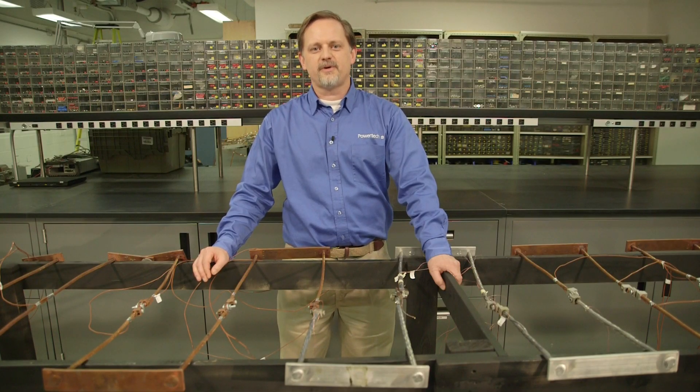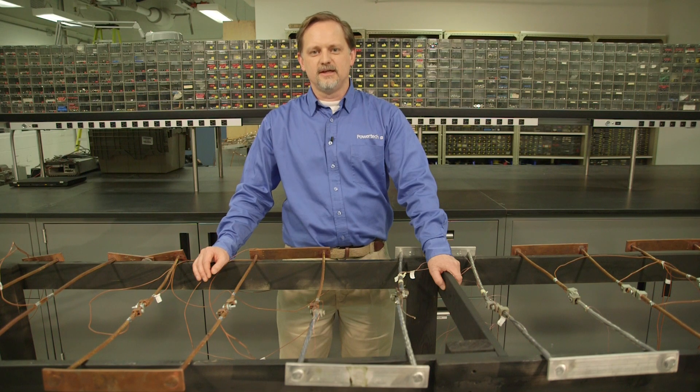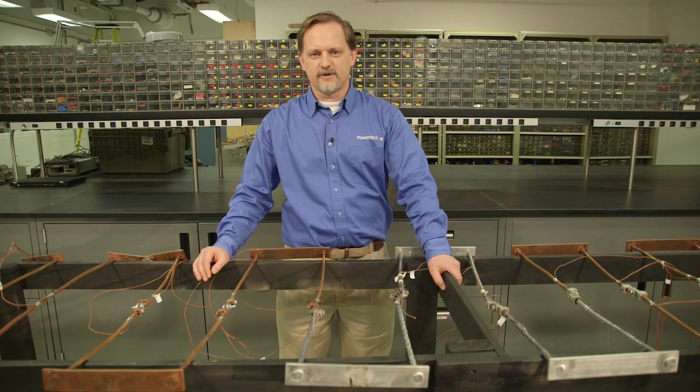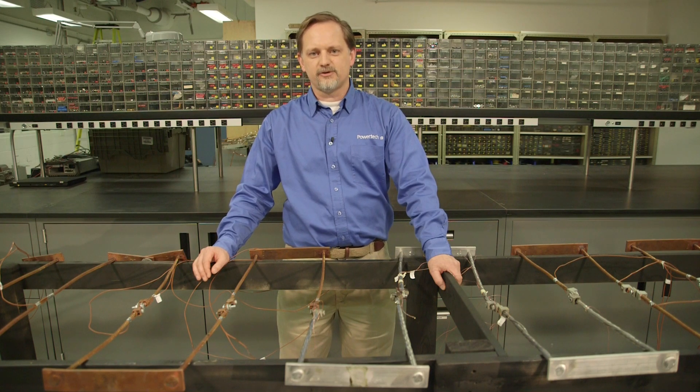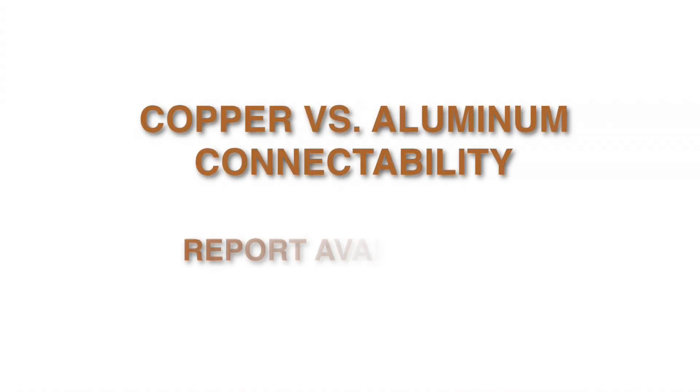To conclude, we saw the best performance in this study with the copper wire and the copper connectors. The next best performance was with the copper wire and the dual rated aluminum connectors. And lastly, the poorest performance was with aluminum wire and aluminum dual-rated connectors. Also, we saw no strong correlation between the sample preparation and the performance of the aluminum wire and aluminum connectors. A full report for this study may be obtained at copper.org.